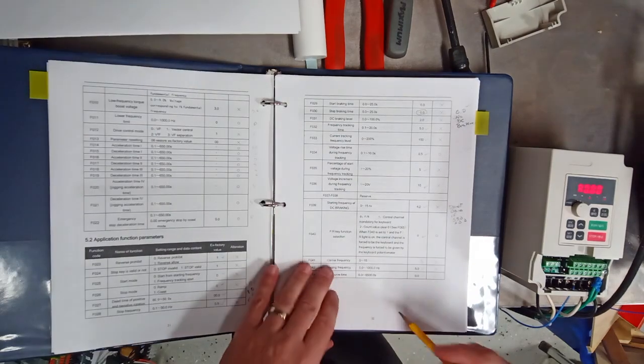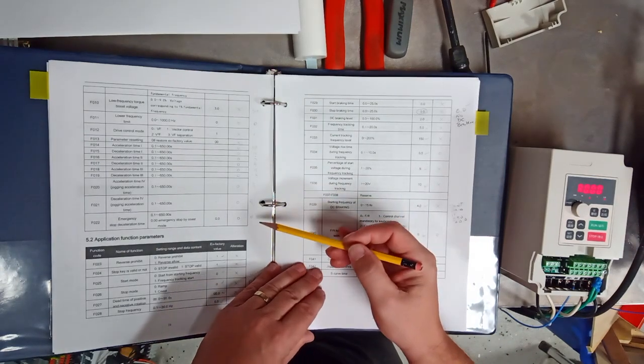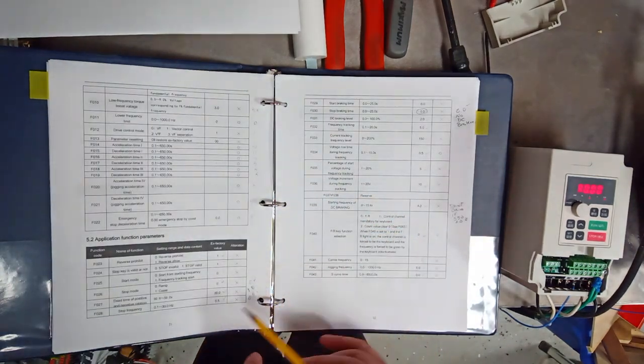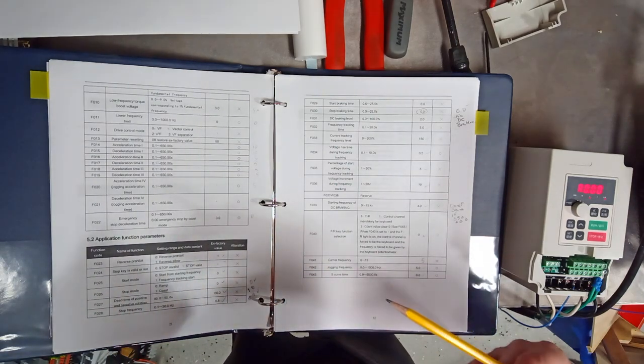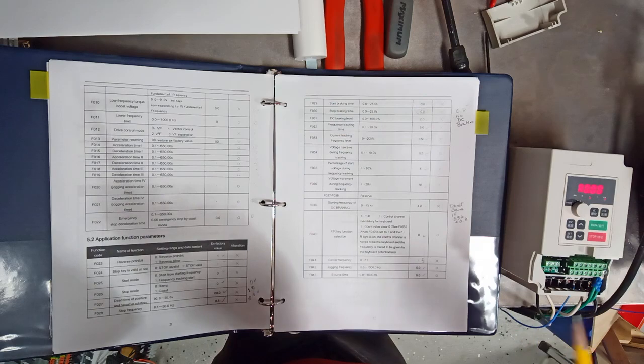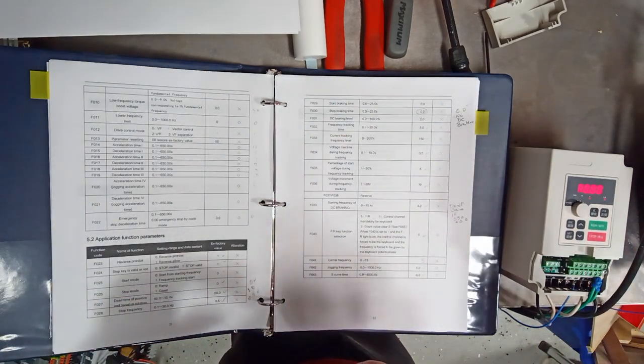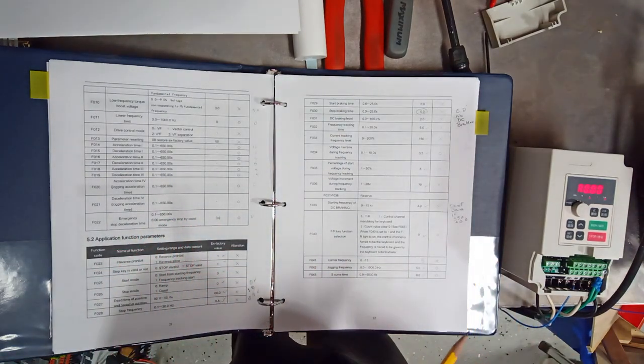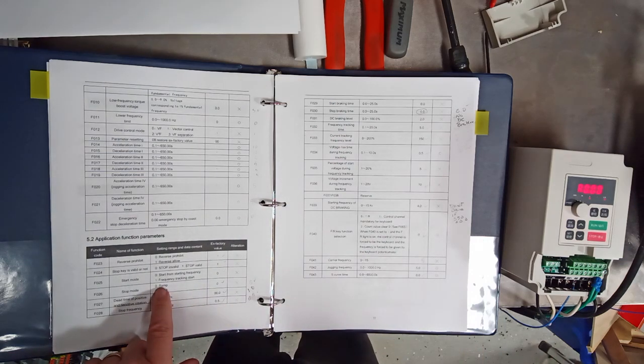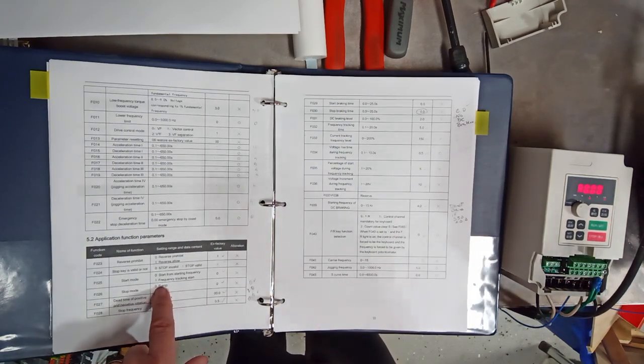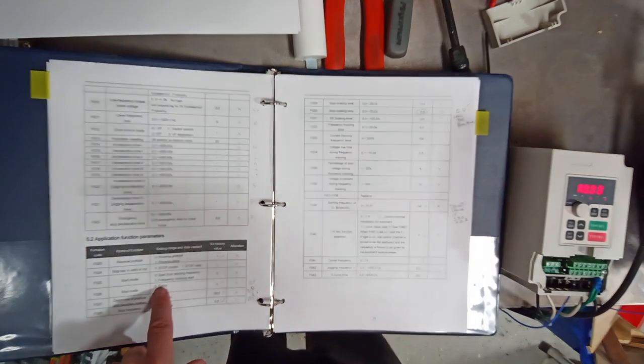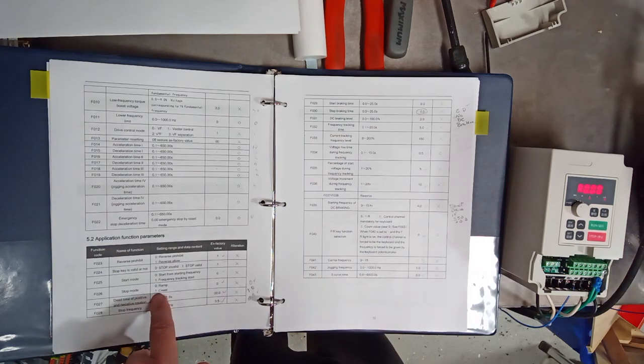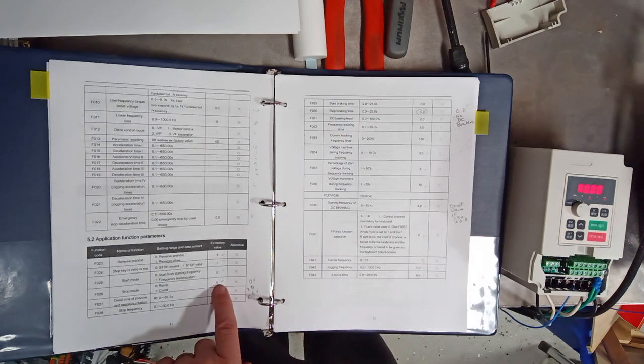The intermediate frequency, these values here are all the stock values that were there, so I didn't do any other changes there. Now, I get into this part here, the stop mode. The VFD has the capability of applying a voltage opposite or switching it around, like as if it's forward and switching the phases around to de-accelerate the motor faster to a stop. So if I'm using a ramp mode, that's what it's going to do. It's going to apply power and slow the motor down faster to a stop than what I used to do with the switch and just turn it off and it would coast. If you want to do coast mode, just like the flipping of the switch on the unit, you'd set that to coast. But I'm using the ramp mode, so I'm leaving it as zero.